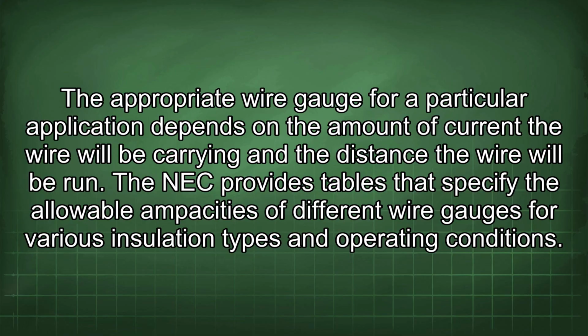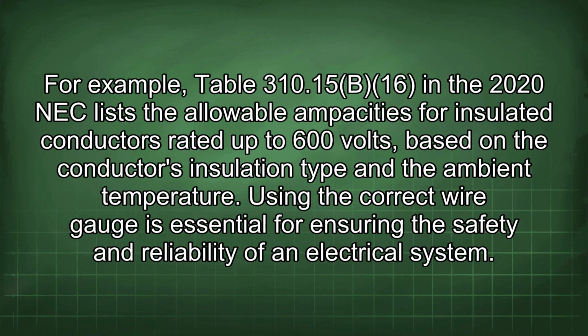The NEC provides tables that specify the allowable ampacities of different wire gauges for various insulation types and operating conditions. For example, Table 310.15(B)(16) in the 2020 NEC lists the allowable ampacities for insulated conductors rated up to 600 volts, based on the conductor's insulation type and the ambient temperature.